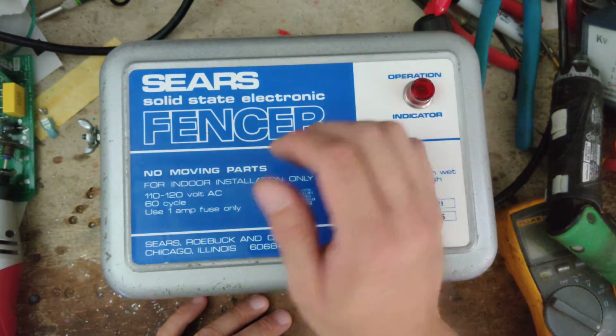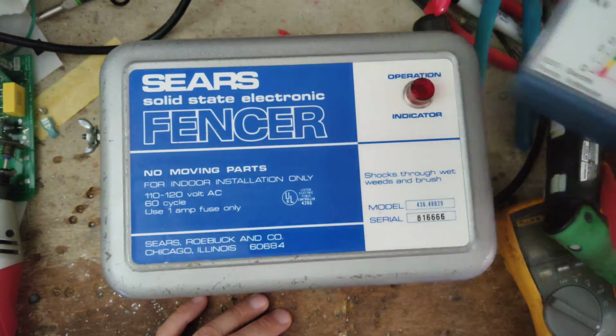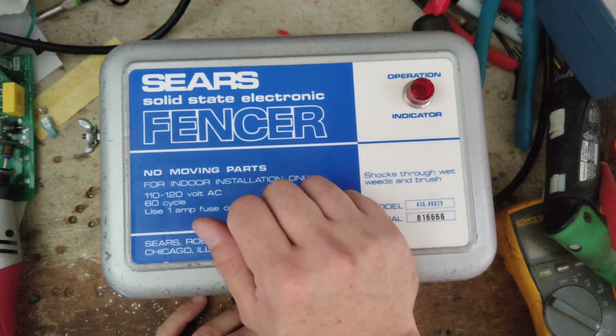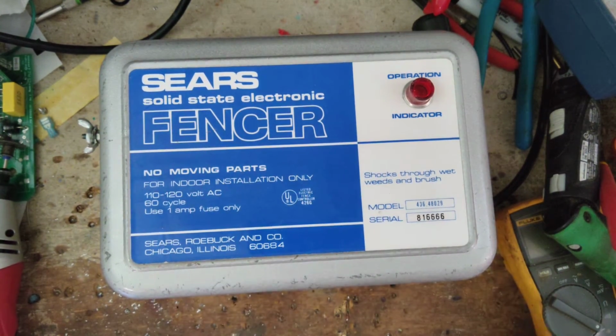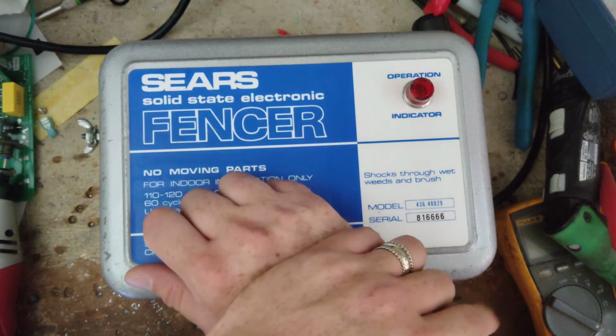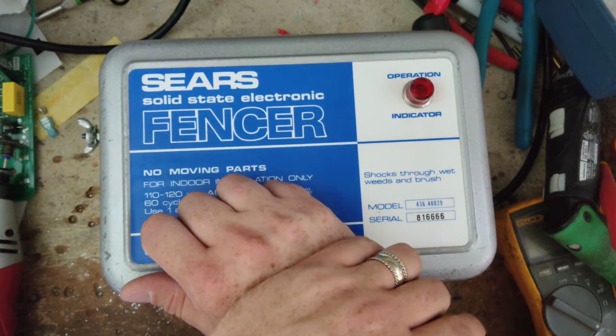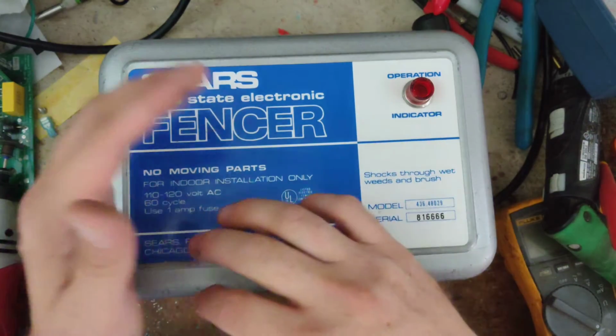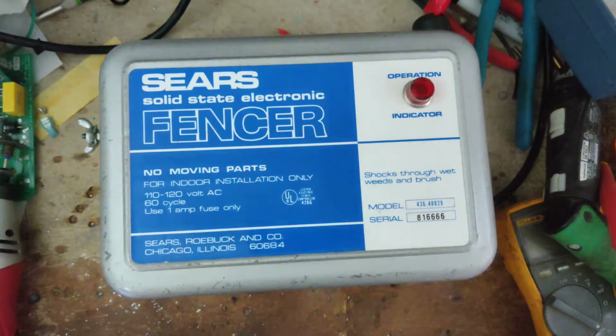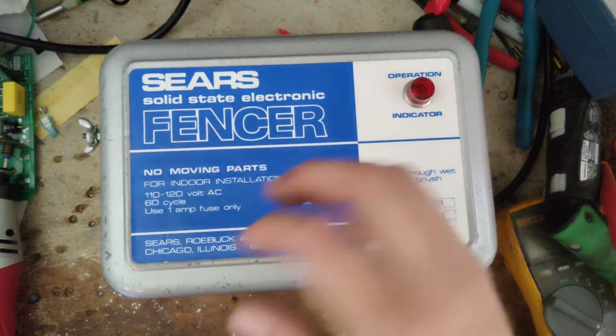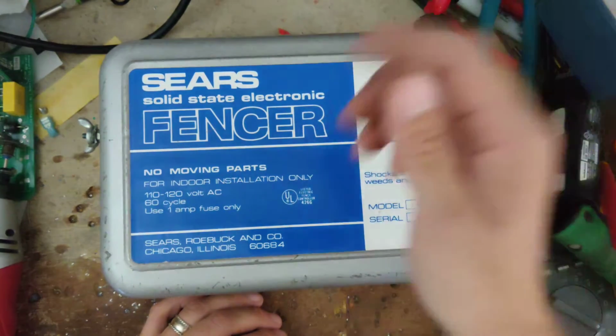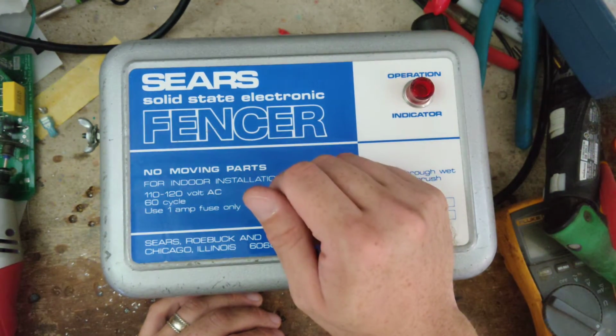It should be 7,000 volts or higher, what these things normally put out. So we got dicking around on the inside and disconnected the transformer from the output just to get that out of the way. We tested it, and the transformer's output didn't change, still putting out real low.